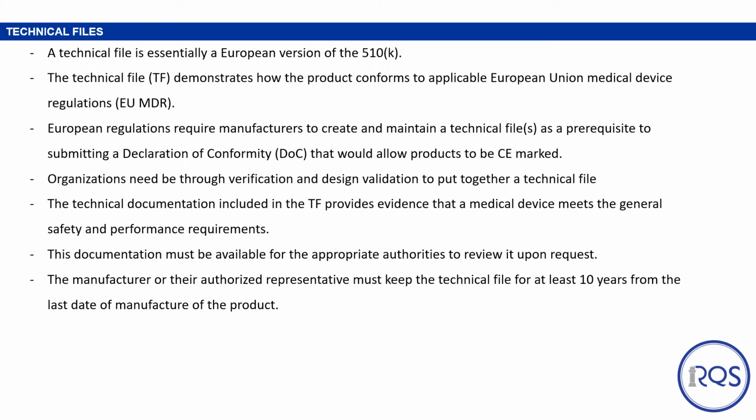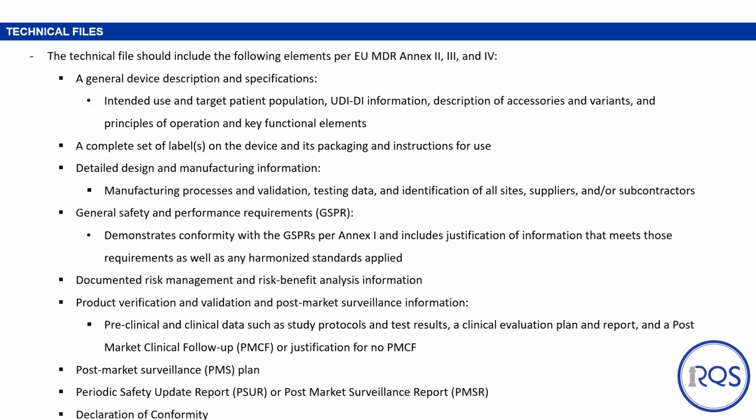The technical documentation included in the TF provides evidence that a medical device meets the general safety and performance requirements. This documentation must be available for the appropriate authorities to review upon request. Usually, the manufacturer or their authorized representative must keep the technical file for at least 10 years from the last date of manufacture of the product. The technical file should include the following elements that are identified in EU MDR Annex 2, 3, and 4.